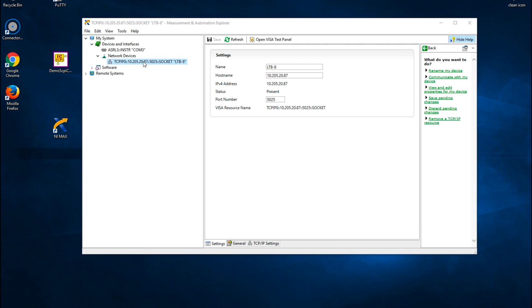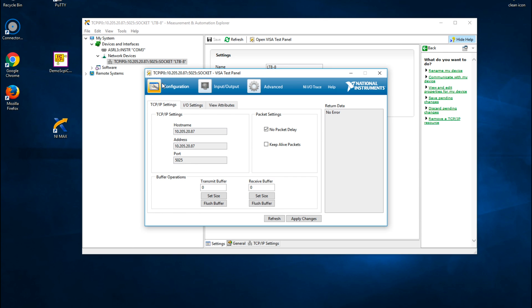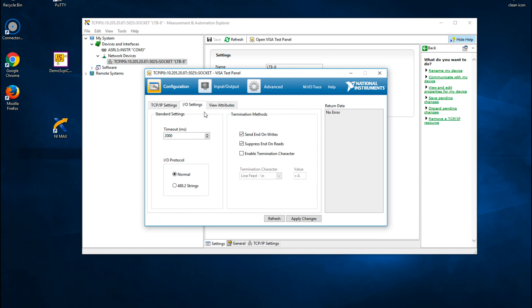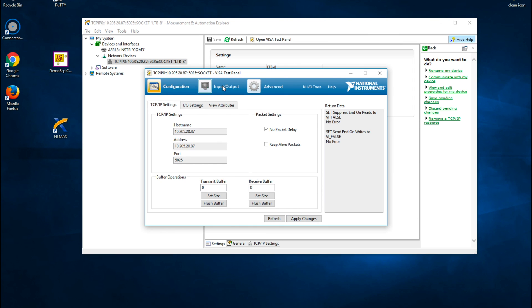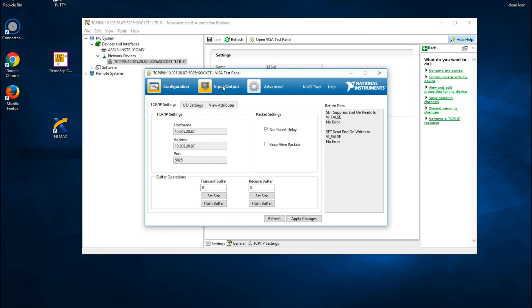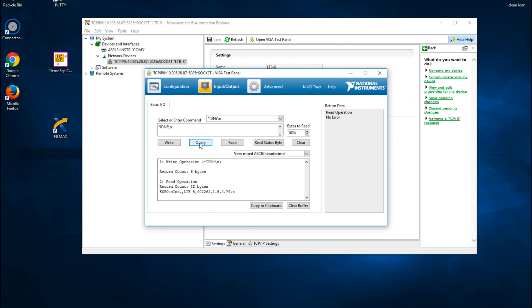The newly added device should be listed under Network Devices with the full name and ALIAS if applicable. Right-click on the device and select Launch VISA Test Panel. In the Configuration tab, go to the I-O Settings and uncheck All Termination Methods checkbox. Then select the Input-Output tab at the top of the Test Panel window. You now have a TCP IP raw socket link established to talk to the LTB-8, just as we did using the Telnet console and remote control demo. Press the Query button and see the result in the text panel below.